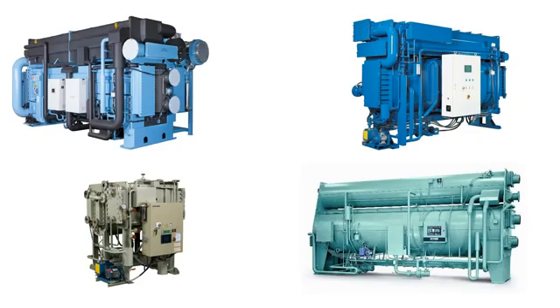how that works. Another interesting point to note about absorption chillers is that they don't use conventional refrigerants such as R134A or R22. Instead, they use water as a refrigerant. And this water is mixed with either ammonia or lithium bromide. Lithium bromide is the more common version, and that's because it's safer and non-toxic. So we're going to be looking at how the water lithium bromide type chillers will work in this video. But essentially they're very similar.